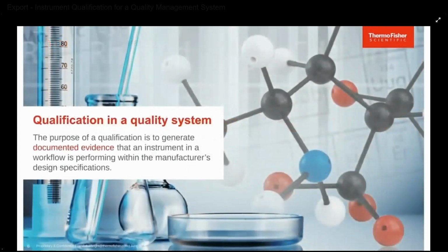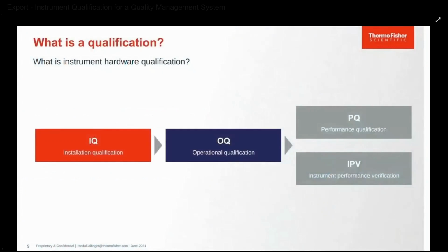The objective of qualification is to produce documented evidence that an instrument in a workflow is performing within the manufacturer's design specification. Again, we want to emphasize the documentation process here. Now that we've established the industry standard origin of the qualification from within regulations and standards for process validation, we can move into what a qualification is. As most of you will be familiar, there are three components to a qualification: installation, operational, and performance. Notice an additional box below PQ on the slide.